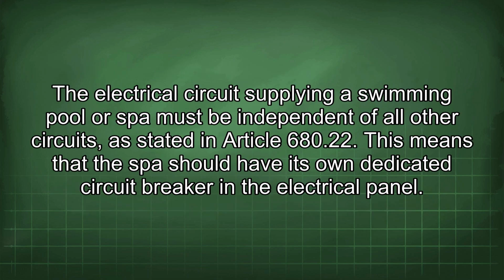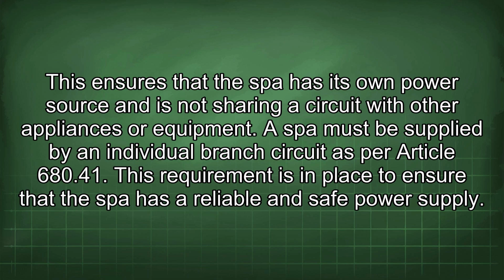The electrical circuit supply in a swimming pool or spa must be independent of all other circuits, as stated in Article 680.22. This means that the spa should have its own dedicated circuit breaker in the electrical panel. This ensures that the spa has its own power source and is not sharing a circuit with other appliances or equipment. A spa must be supplied by an individual branch circuit as per Article 680.41. This requirement is in place to ensure that the spa has a reliable and safe power supply.